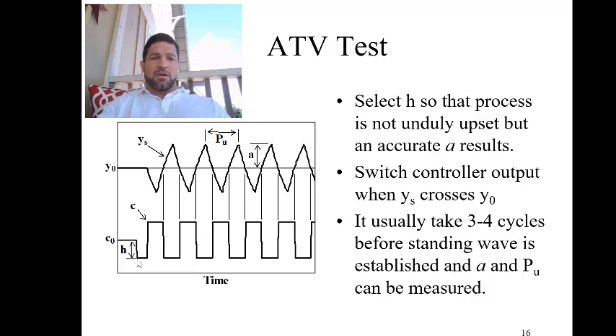So we step down, wait for the system to respond. You can see as we step down it takes a minute for the system to actually respond shown here. And then as soon as the system starts responding we step up. Because the system takes a while to respond, it'll start going back to the steady state. And as soon as it crosses the steady state we can switch the controller back in the opposite direction.